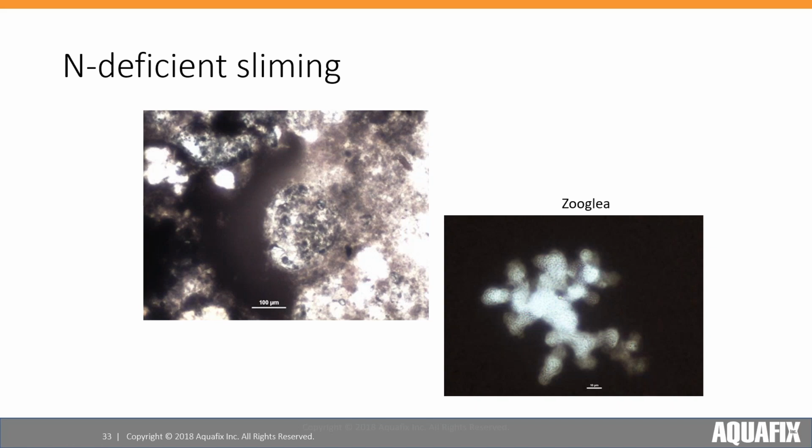If you have foaming filaments also present, sliming may make foaming worse. That's because these flocks with a lot of slime are actually pretty weak in shear strength. So they also are very light and they tend to float. And that's why you might see them carry over with foam or just with the water movement and increase your TSS.